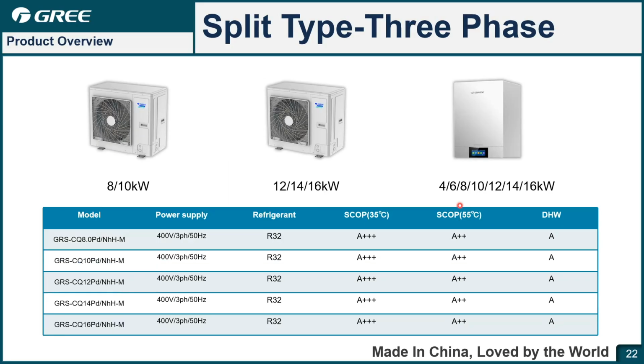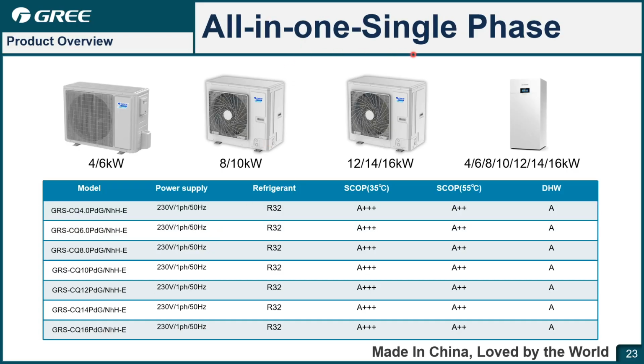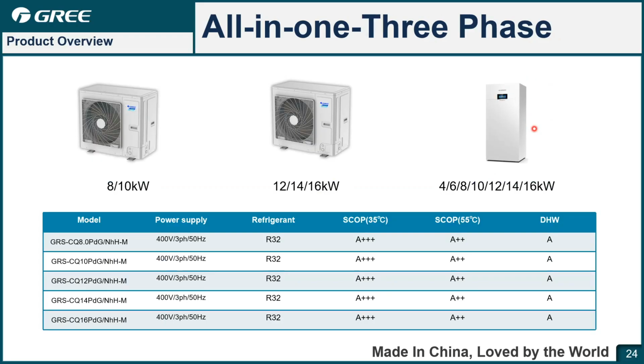This is a single phase, and another one, split type 3 phase. The basic capacity is from 8 kilowatts to 16 kilowatts. However, the hydro box is still the same here, and the power supply is 400 volts. For the all-in-one single phase, the capacity is also from 4 kilowatts to 16 kilowatts here. For the hydro box and the water tank, they are the same. They share the same model. And for the 3 phase all-in-one VERSATI 3, the minimum is 8 kilowatts, maximum 16 kilowatts. Also share the same indoor unit.